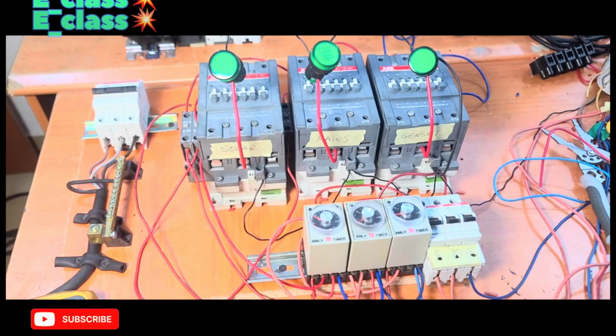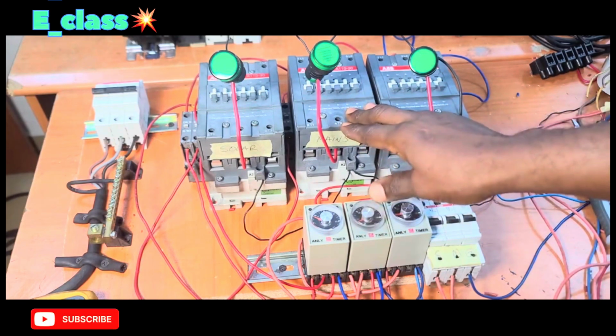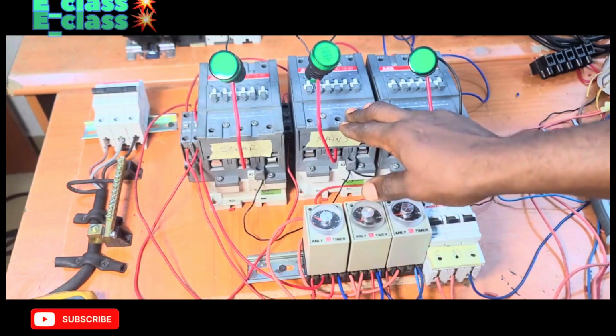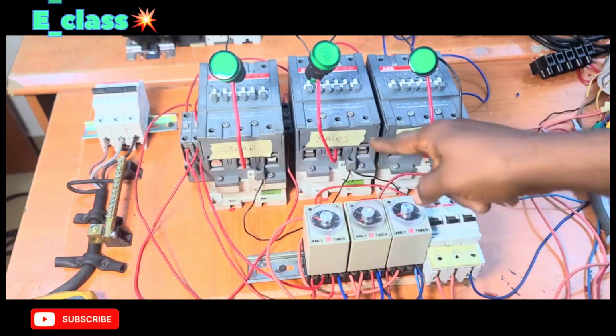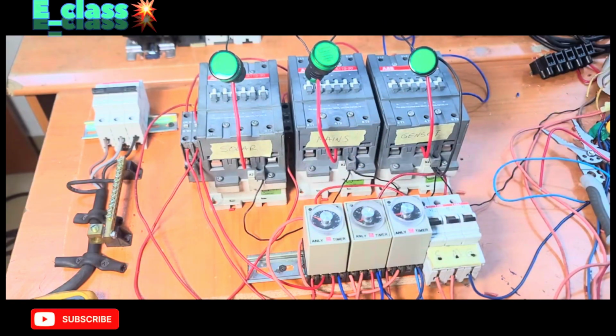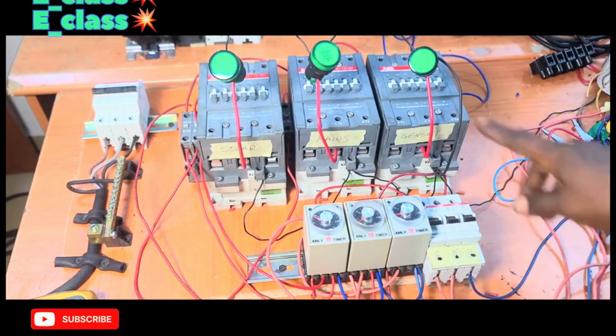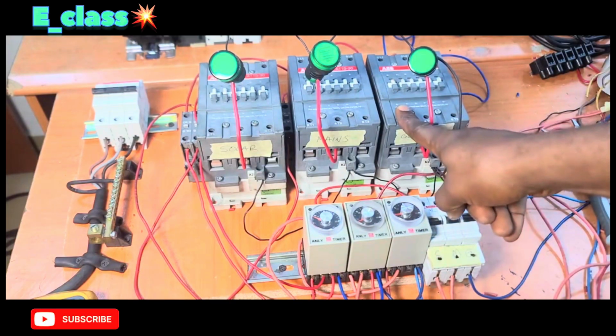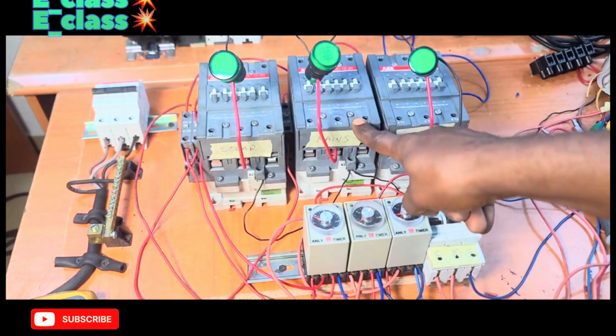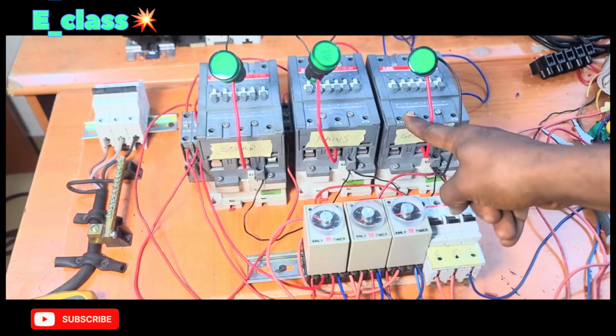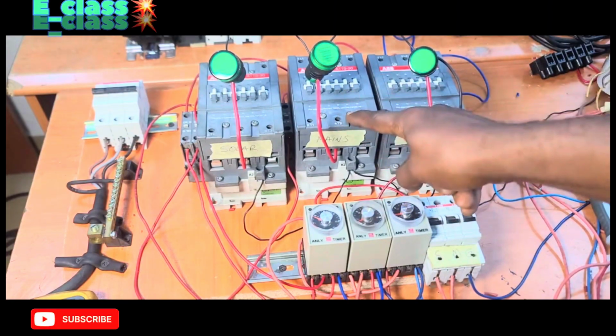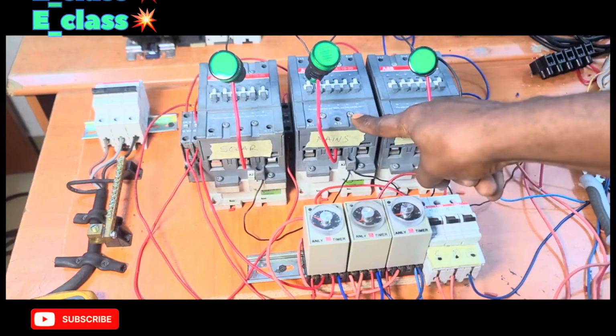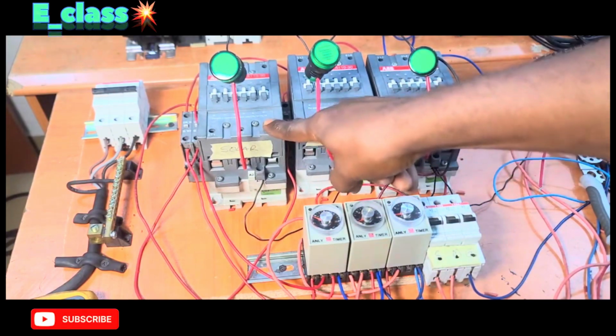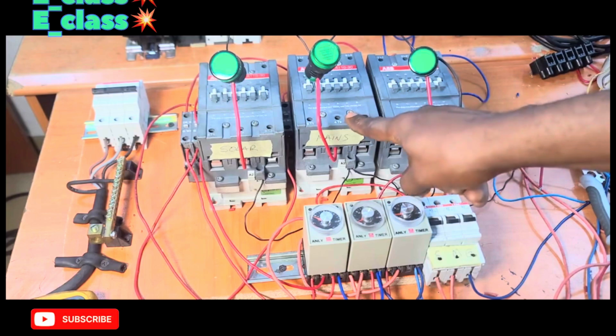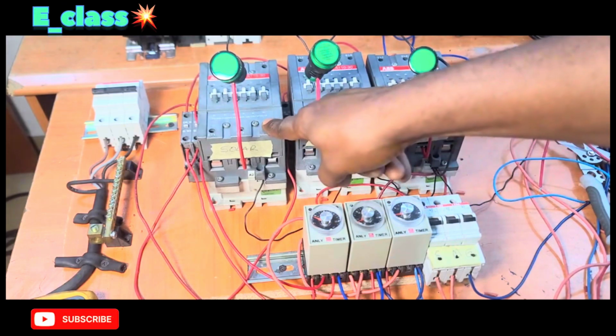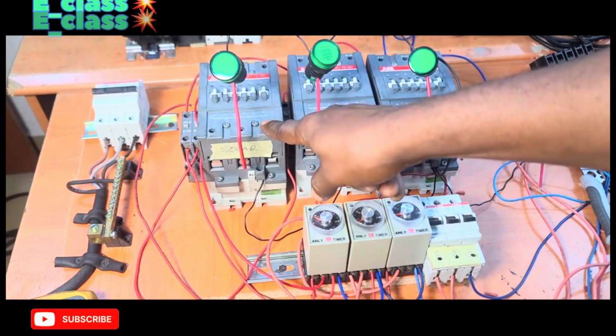Yesterday, we went through this automatic changeover switch with 3 different power sources, which are solar, mains, and generator. And we were able to operate it so that when this one is on and mains is restored, it will immediately cut off this one, delay for some seconds, and energize this one. If this one is on and solar is up and active, it will disconnect this one instantly and delay for some seconds before it energizes this one.